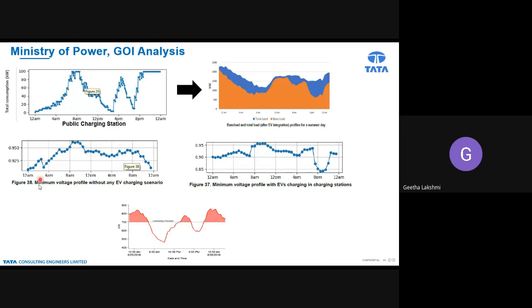We can see here the minimum voltage profile without any EV, around 0.9, that is 90%. Whereas with EV, the minimum percentage drops to below 85%. All electrical appliances are designed for plus or minus 10%, that is 90%, but here at evening time it drops even below 85%. So transformers and every appliance may see this dip in the curve. This is quite severe, and we can even see the maximum drop is not favorable either, around 96%.